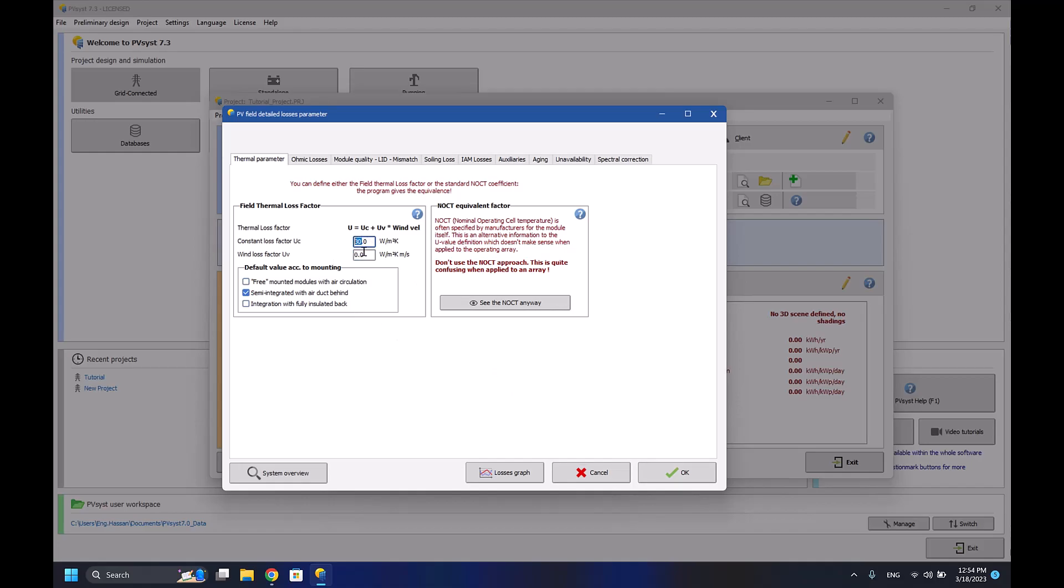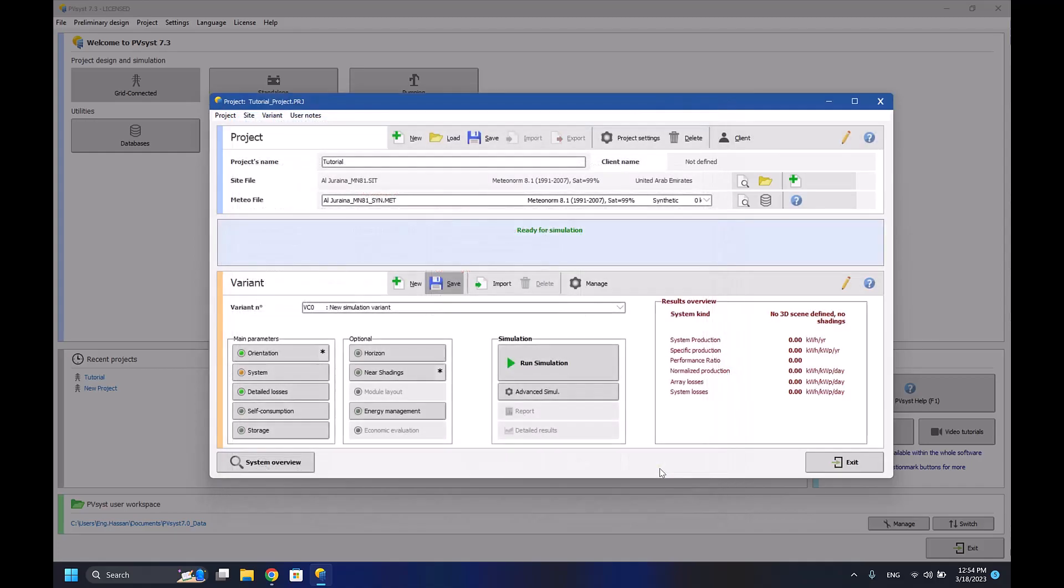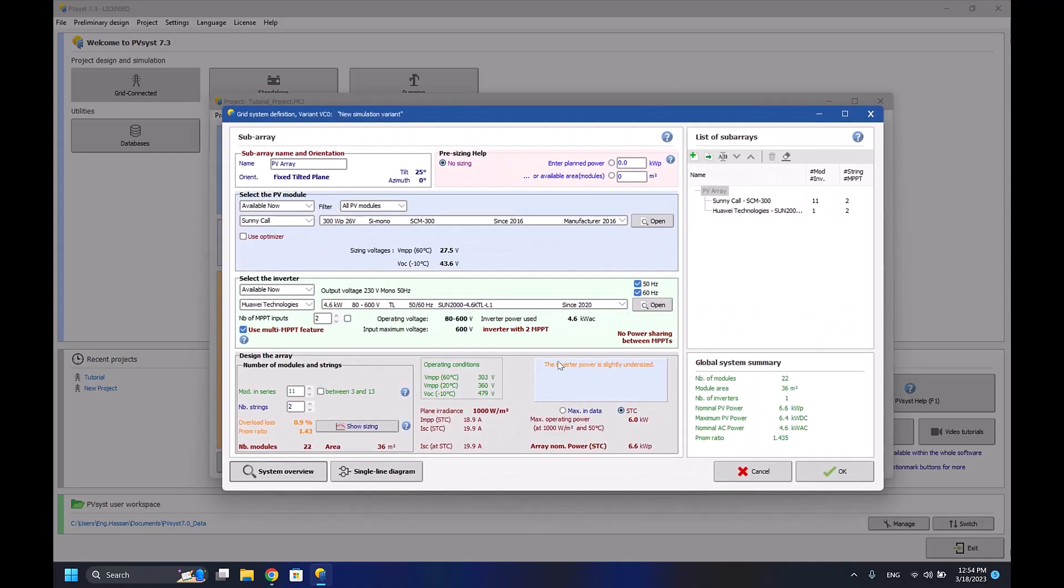It's really important to note that if I change the constant loss factor to, let's say for example, 35 watt per meter squared kelvin and I press OK, I'll have error in my system which says the inverter power is slightly undersized. That's because the overload losses is higher now.